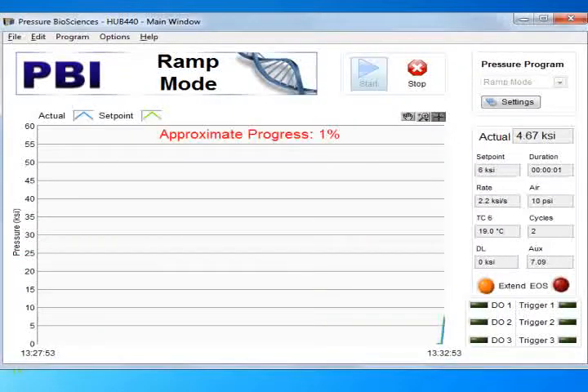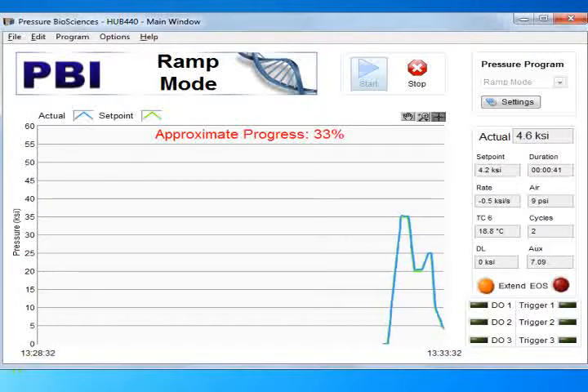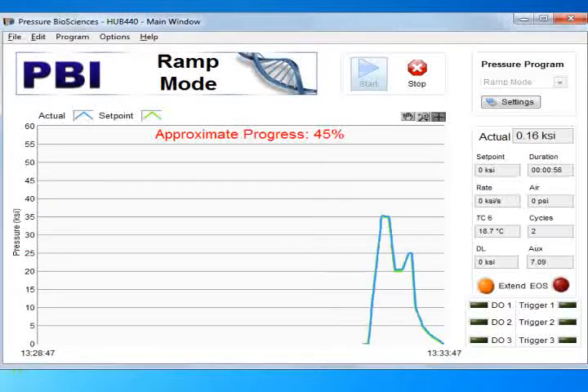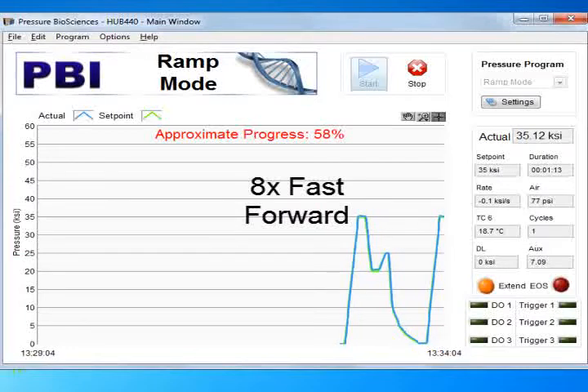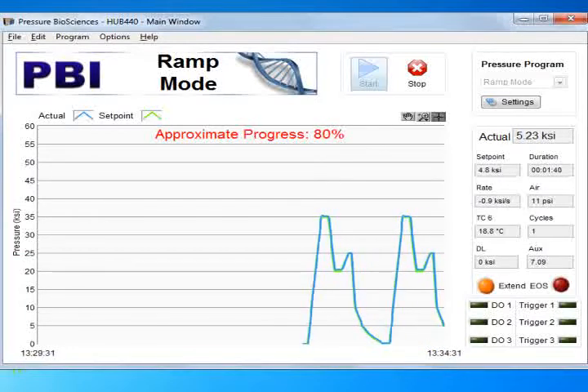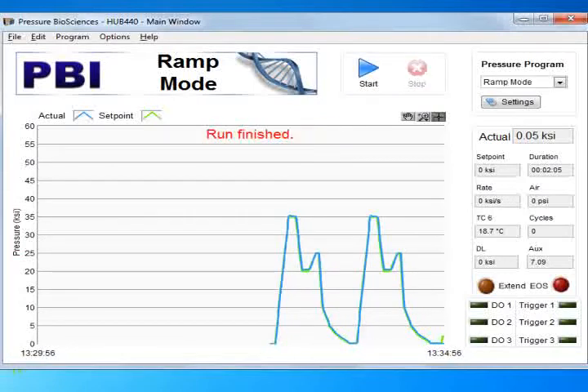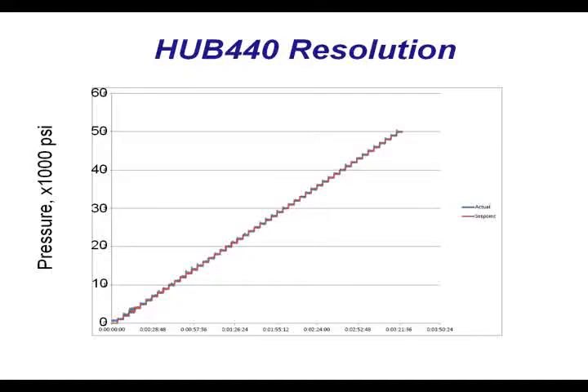Followed by the prompt for the log file name, the program begins. As previously, we will show you the first cycle and then fast forward the program to illustrate the second cycle. The resolution of pressure control is approximately 100 psi as shown on this graph. Built-in PID logic option maintains pressure at specified value for processes that occur at rapidly changing temperatures.